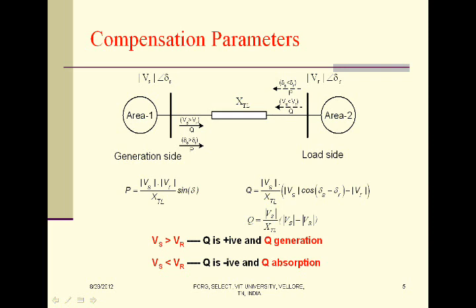Coming to reactive power, it depends upon the voltage difference between the sending-end voltage and the receiving-end voltage. If sending-end voltage is greater than receiving-end voltage, then the transmission line is inductive in nature and we have to inject reactive power into the system. If sending-end voltage is less than the receiving-end voltage, then the transmission line reactance is capacitive in nature, and we have to absorb the reactive power from the system in order to maintain the voltage profile.